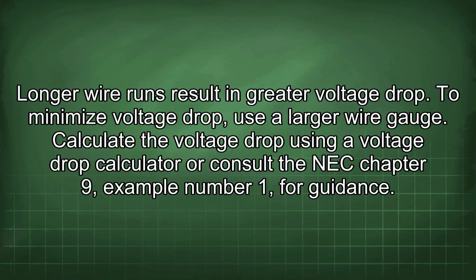Longer wire runs result in greater voltage drop. To minimize voltage drop, use a larger wire gauge. Calculate the voltage drop using a voltage drop calculator or consult the NEC Chapter 9, example number 1, for guidance.